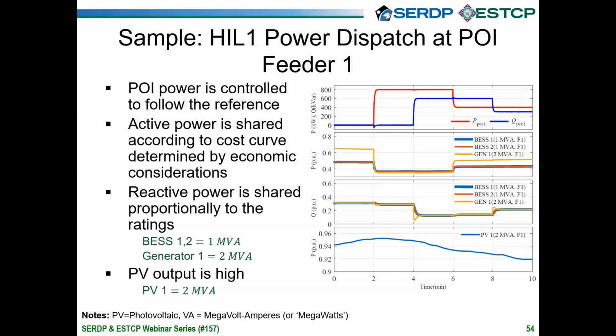Now, here the trick is that the battery and the gensets have some ratings, and the ratings may be different. And what these algorithms can do is share the power proportionally according to the rating among the different elements. So in this particular example, the batteries are 1 MVA and the genset is 2 MVA. We also have a PV in the system, and the PV output is rather high, but it's rated at 2 MVA. So this shows that the control algorithms are able to implement this proportional power sharing in this mode of operation.